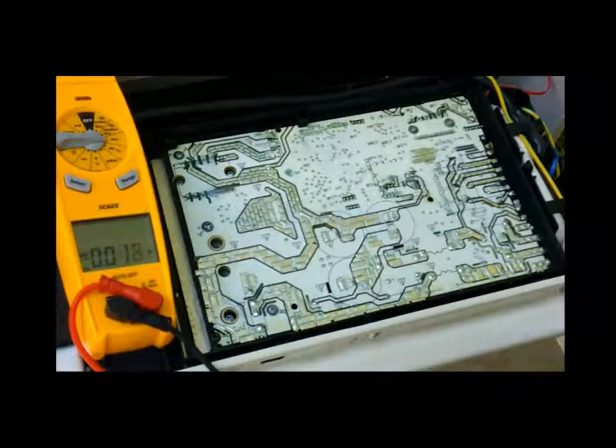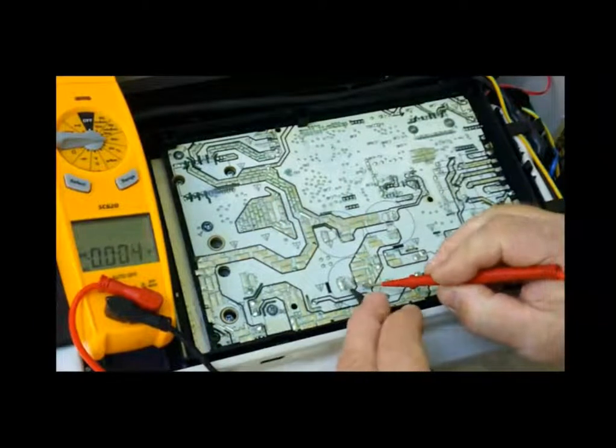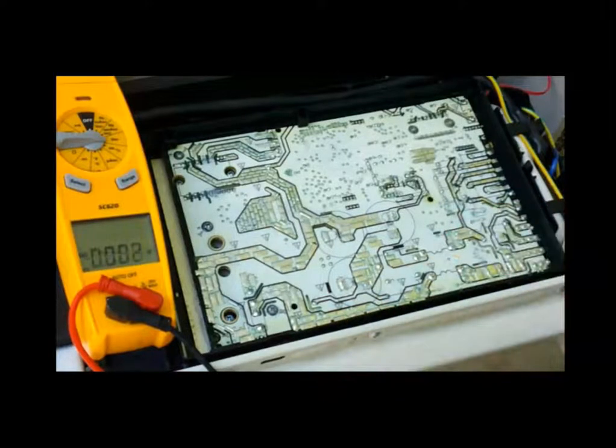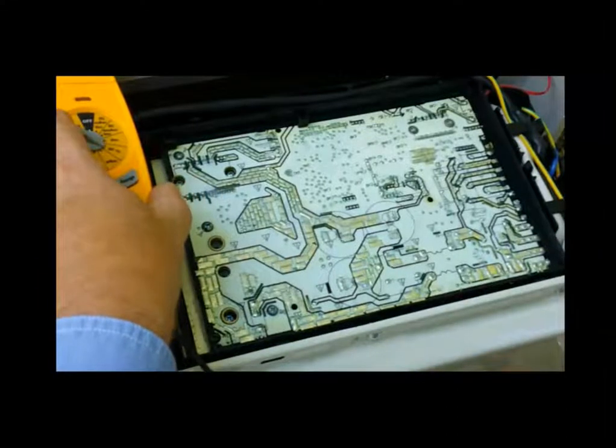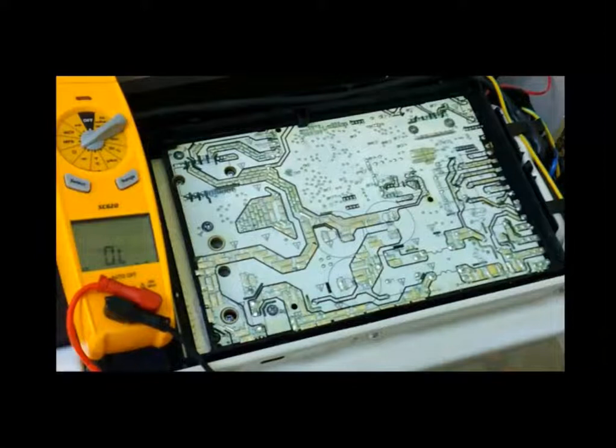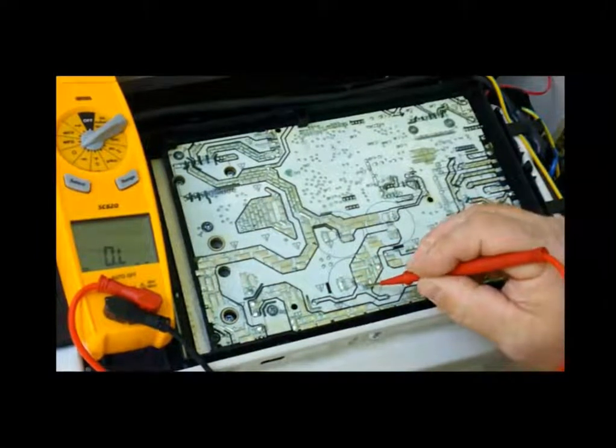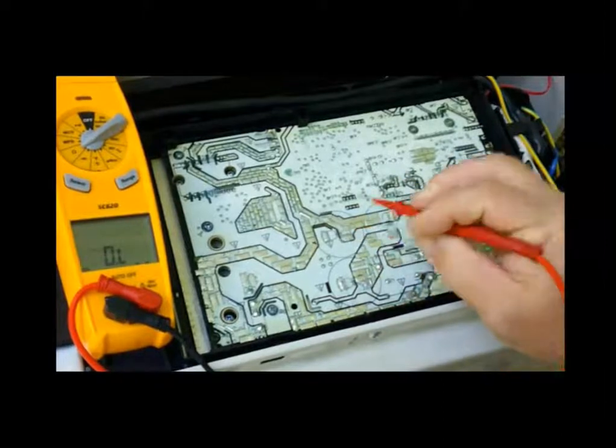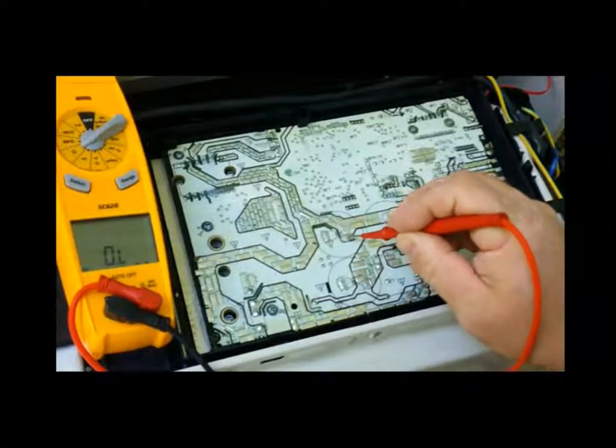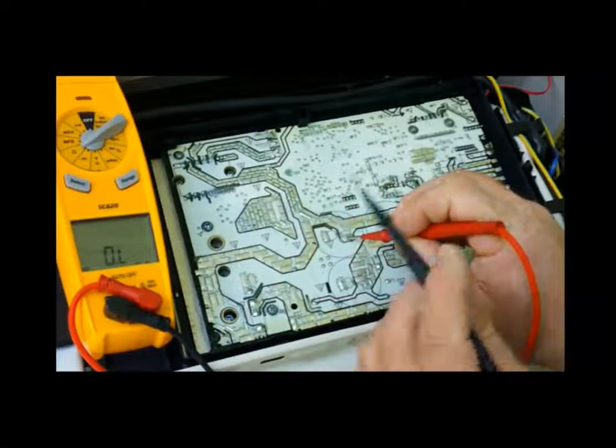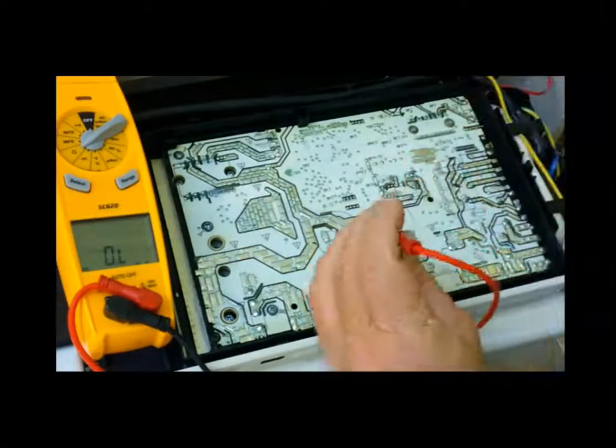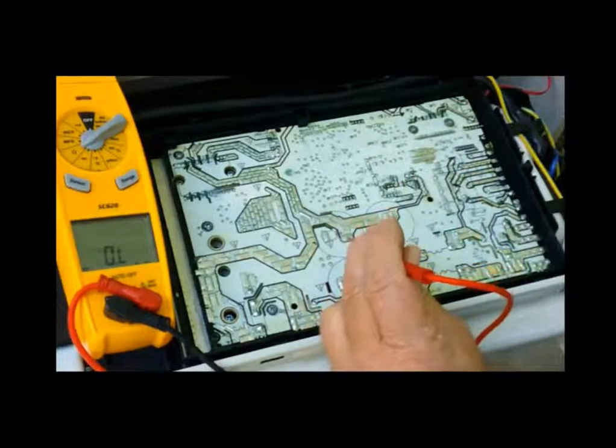Then we're going to do a double check. We're going to flip it over to DC voltage. We're going to check our capacitors. And you can see we dropped down. We're at 9.3 volts. So they're discharged enough for us to go ahead and do this test. Now what we're going to do is flip it over to ohms. We're going to check it on megaohms. We're going to take our red and we're going to put that down on the positive side of one of our capacitors. Then we're going to locate the UVW that goes to our compressor.